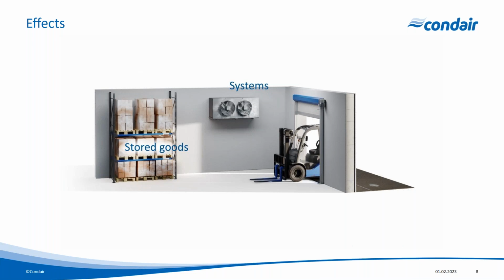So any moisture that's going to come into contact with that coil potentially can freeze. And it's usually the first place that it does freeze because we've got fans moving the air and circulating air. So more of the air is going to come in contact with that evaporator coil. So then we get ice forming more readily. But that's not the only system. We could have smoke detection systems. Smoke detection systems have very fine filters in them, and small ice crystals can block up those filters very quickly. We could have fast-acting doors. We could have switches on those doors that are going to be affected by that ice. So systems can be dramatically affected by ice in the space.